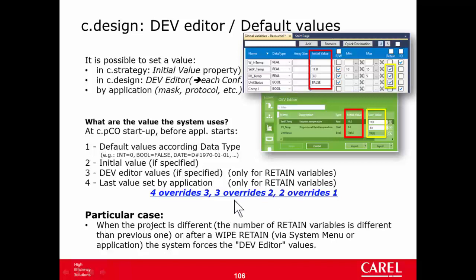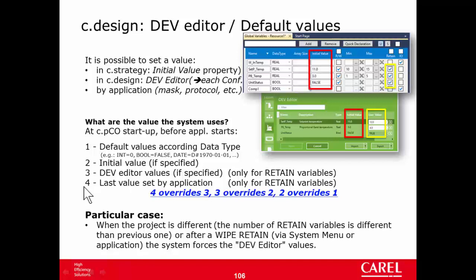Let's look at some typical use cases. The first could be Compressor 1, which has no initial value and is not retained. At startup, Compressor 1 takes the value false, since it is boolean. The initial value is not specified, so it remains false. The DEV value does not apply because this is not retained, so it remains false. The last value set by application also only applies to retained variables, so it remains false.